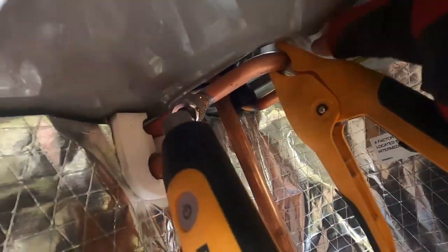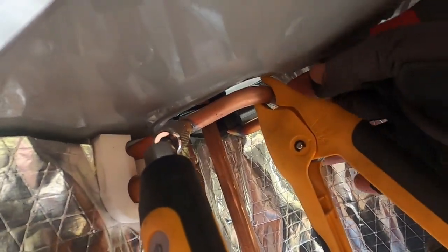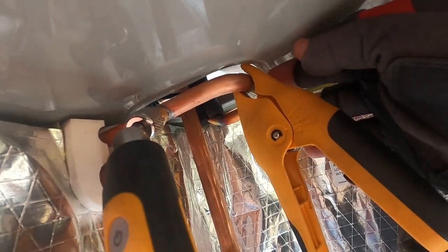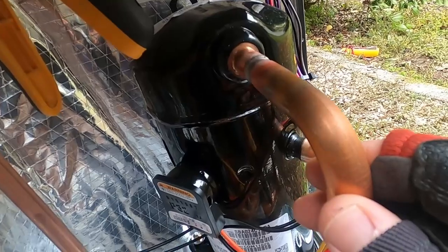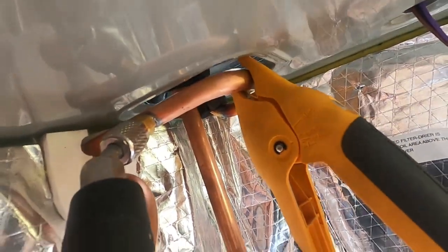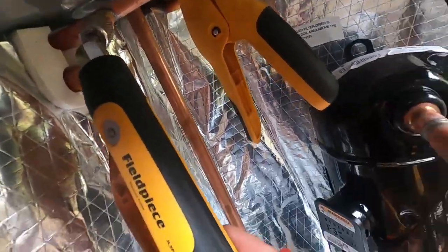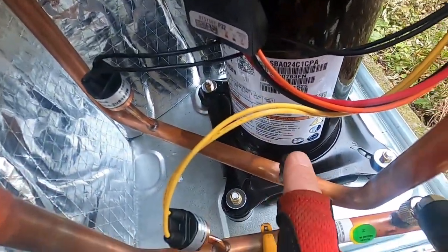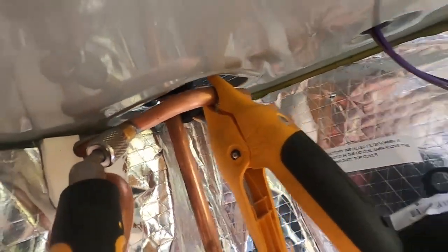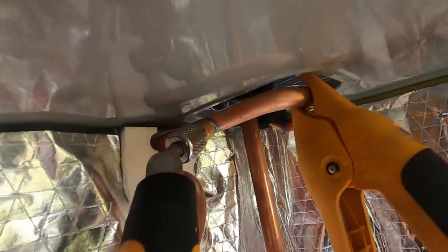Make sure you always get your subcooling reading from this pipe up here. That's your actual liquid line going back to the coil. Don't hook up to that. That's hot. Hook up to this line up here to get your subcooling. See, I've got my probe hooked there. They do put a discharge fitting there, but you want to hook up to your liquid line in these Trane package units. That's the proper location to hook up to.